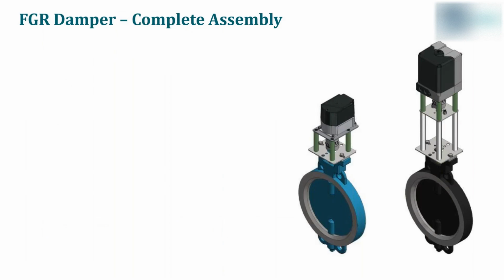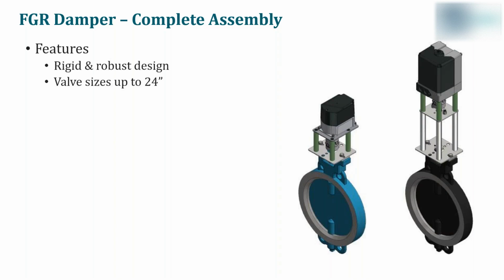Now, SCC also offers a complete FGR assembly. Therefore, if a customer chooses to replace an existing FGR valve, we have the capability to supply this. FGR assemblies are wafer-style valves. These assemblies are designed for both thermal expansion and contraction. Therefore, it eliminates the possibility of the valve seizing up.